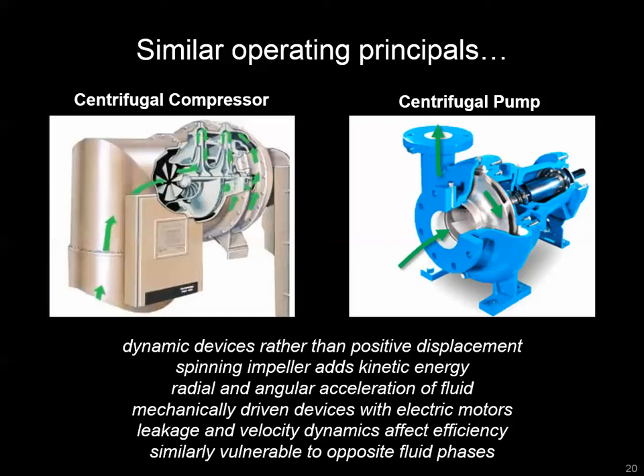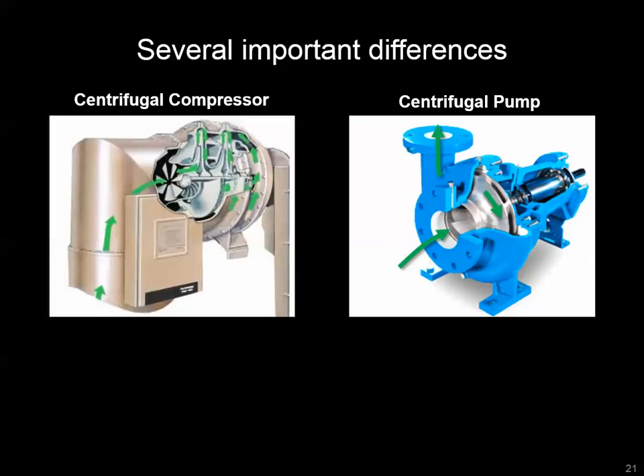Both devices are susceptible to damage from having a fluid other than what they were designed for. In the case of the compressor, we talked about slugging and flooding — where you have the liquid phase of the refrigerant going through or near the compressor. With the centrifugal pump, we're going to talk about cavitation, where you have vapor bubbles at the impeller and what damage that can cause.